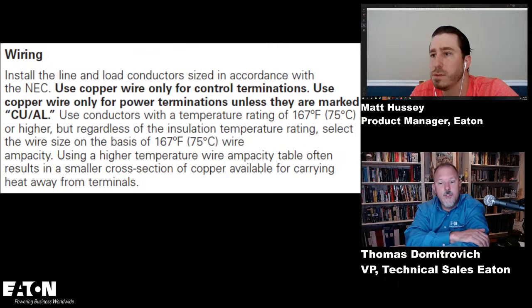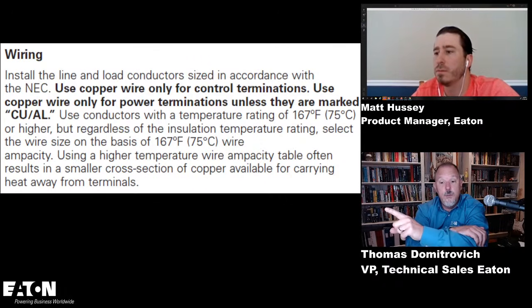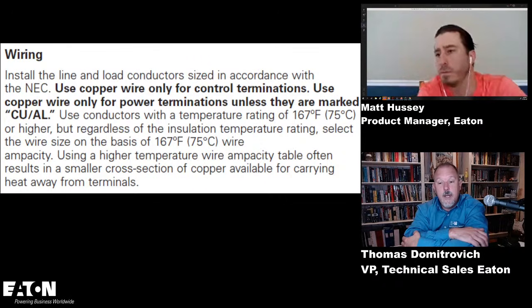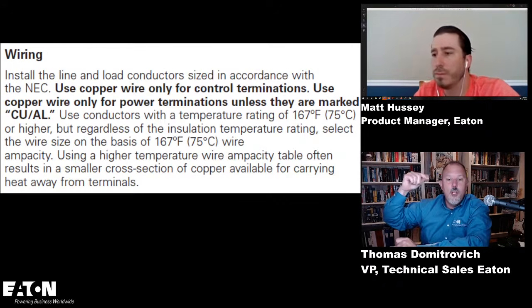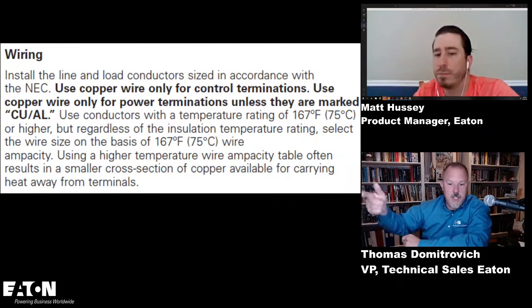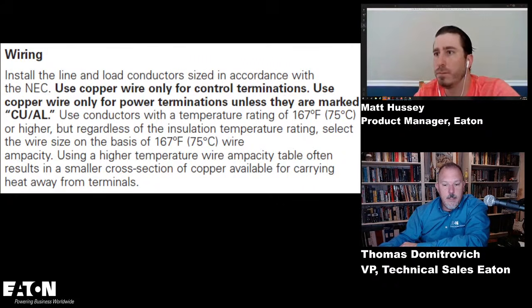But it says for power terminations, use copper wire only unless they are marked CUAL, copper aluminum. Conductors with temperature ratings of 75 degrees C or higher. It says or higher because we have to remember, I can wire with 90 degrees C insulation, but I still have to use the 75 degrees C column as per our 110.14 requirements. Regardless of the insulation temperature rating, select the wire size on the basis of a 75 degree C wire. What that means is you select it based upon the ampacity of a 75 degree C wire.